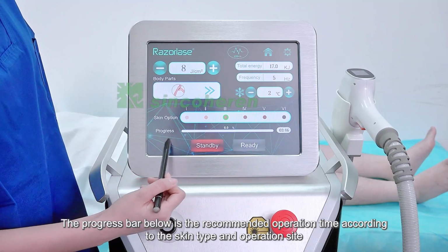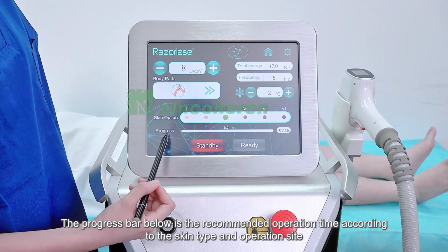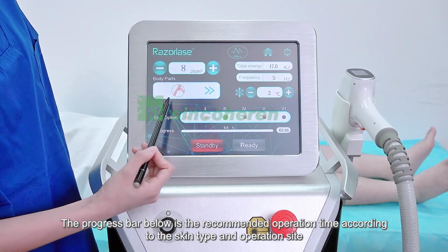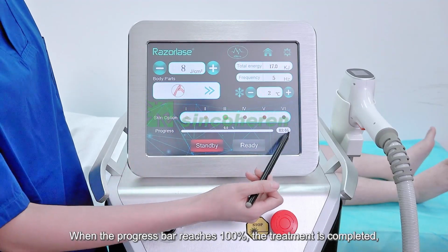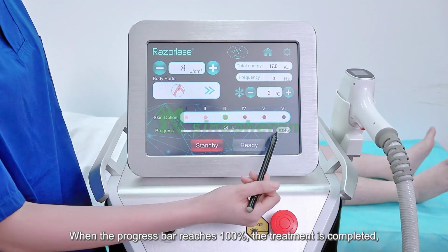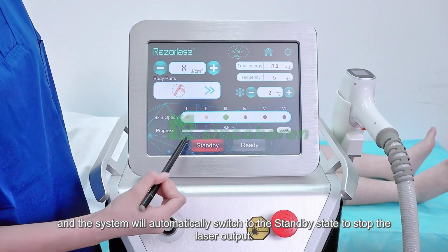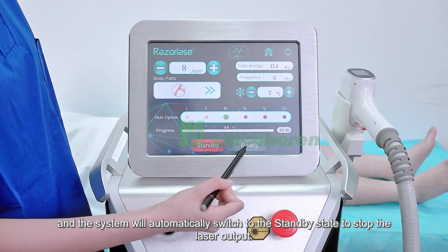The progress bar below is the recommended operation time according to the skin type and operation site. When the progress bar reaches 100%, the treatment is completed, and the system will automatically switch to the standby state to stop the laser output.